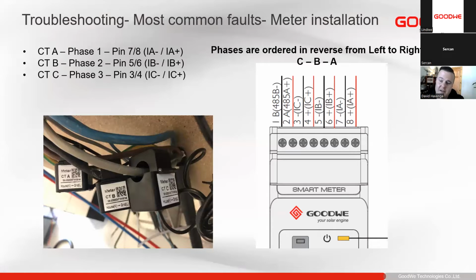You can find our user manual for the smart meter. We also do have an indication on the side of the smart meter, but I always urge you to take photos, mark your cables clearly, and make sure that we install them back correctly. Because this also makes it very hard to troubleshoot if these have been changed. So remotely we can do very little to help if this is wrong, but typically if you have removed these, please pay careful attention to make sure you've installed them correctly back.